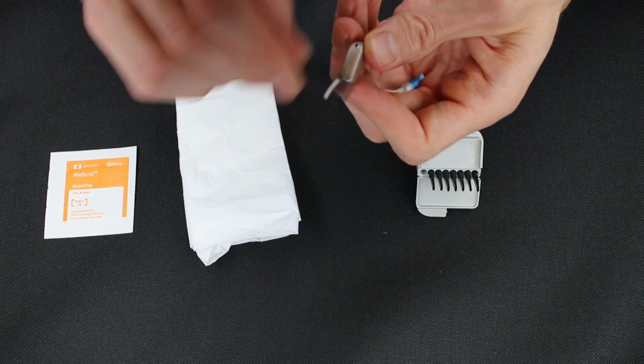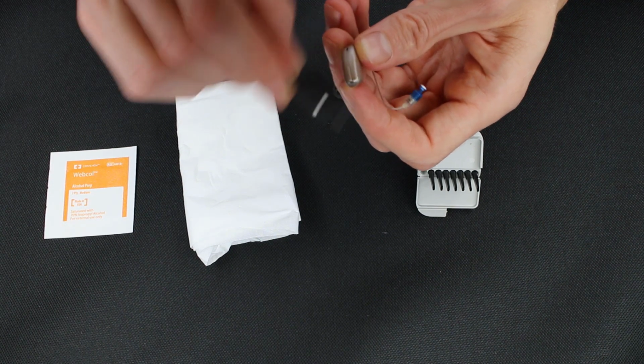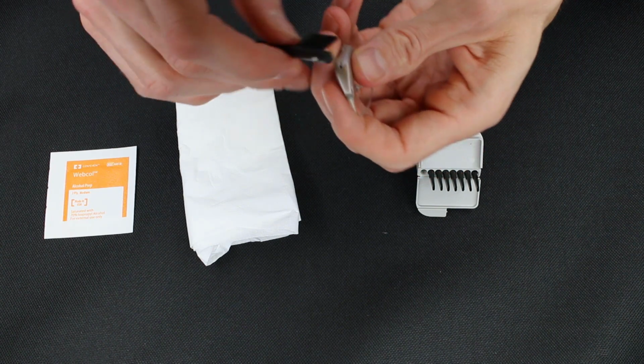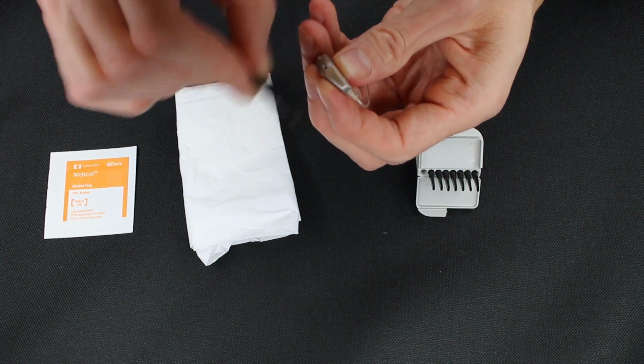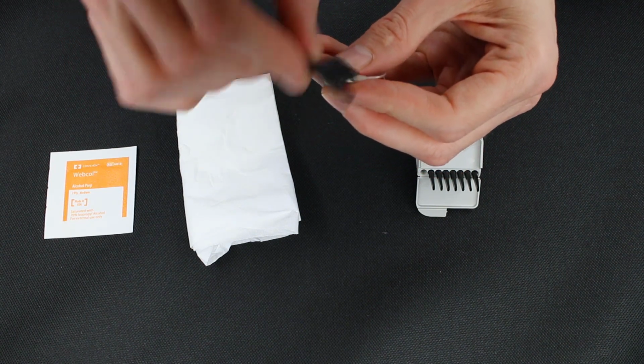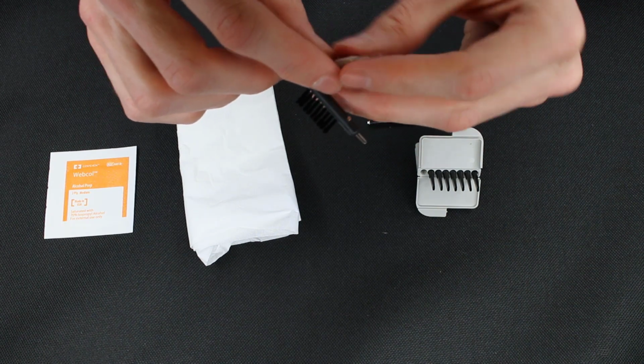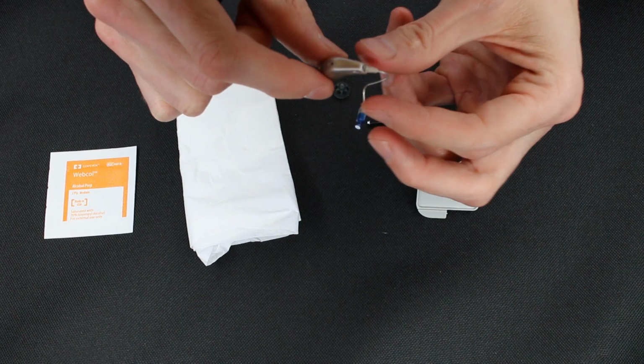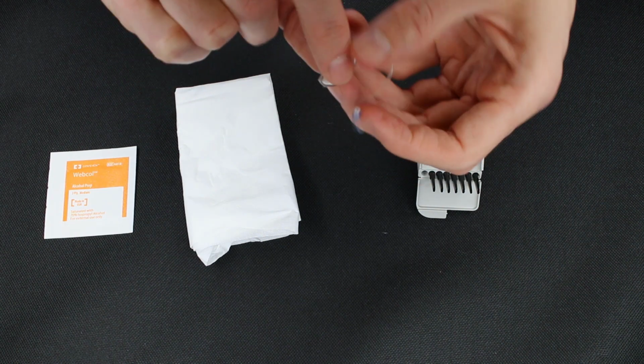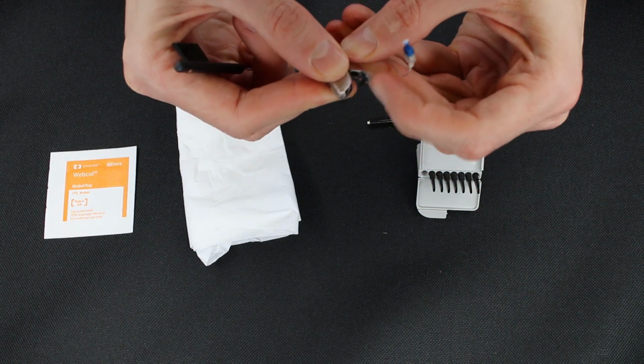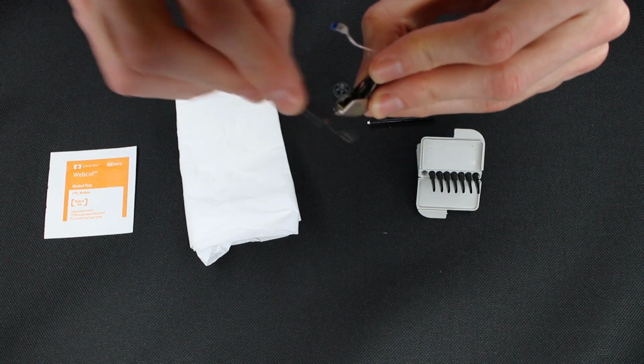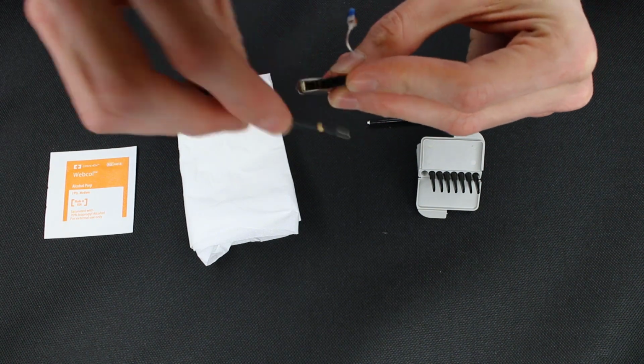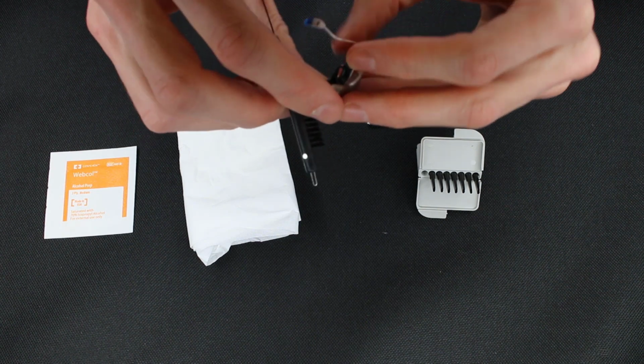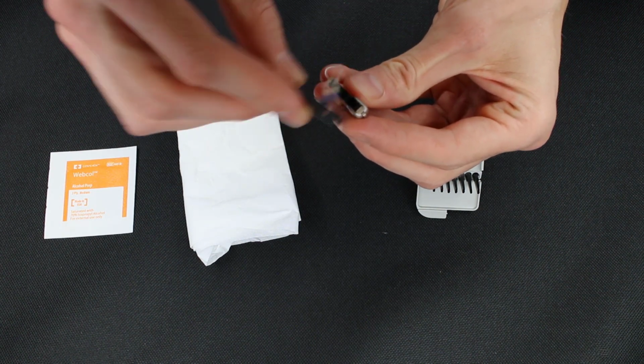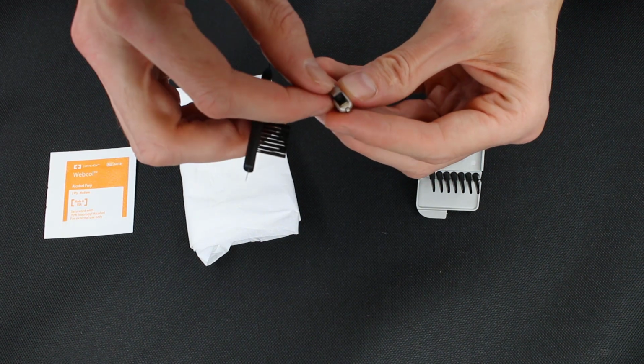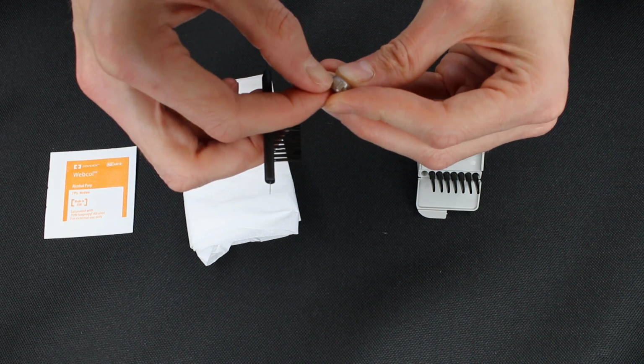If any debris gets into where that push button is, it will prevent that button from working. And same thing with the microphones. If we have any debris over the microphones, we want to make sure that we keep that out of there, otherwise it won't actually pick up sound to amplify. What we can also do is open up the battery door and brush out any debris that's inside of the battery compartment. If too much debris builds up in there, the battery won't make contact with the battery contacts and the hearing aid won't turn on.